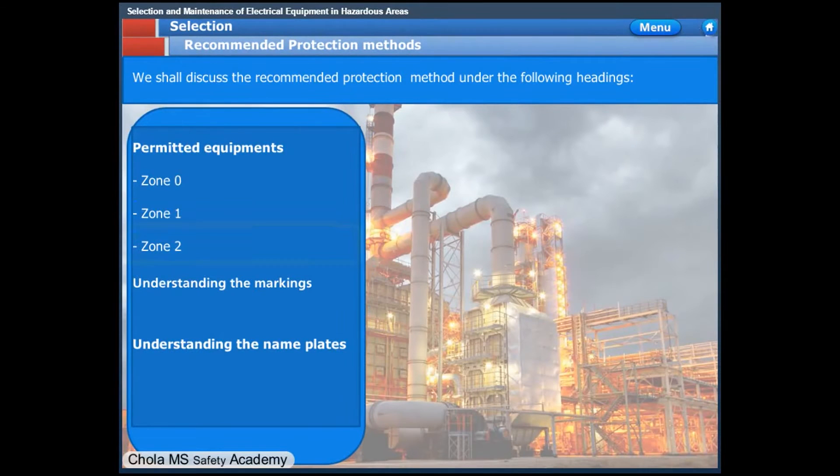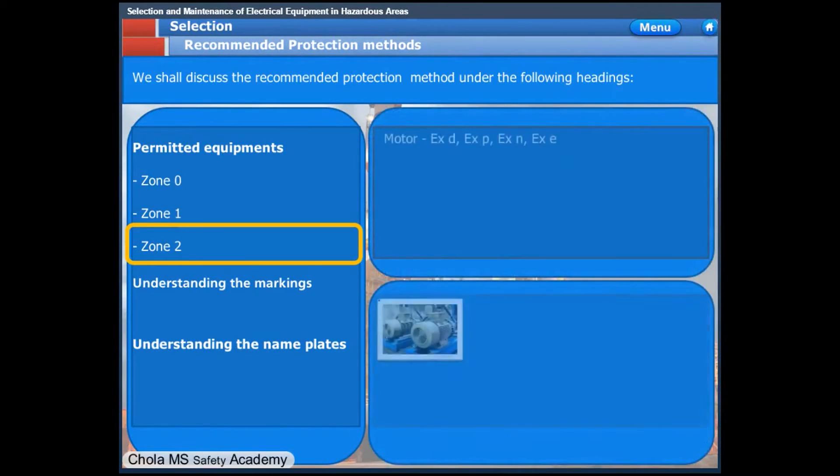In Zone 2 classified areas, the motors shall be flame-proof or pressurized enclosure type — as in Zone 1 areas — or Ex n non-sparking type or Ex e increased safety type. All Zone 1 apparatus are acceptable in Zone 2.